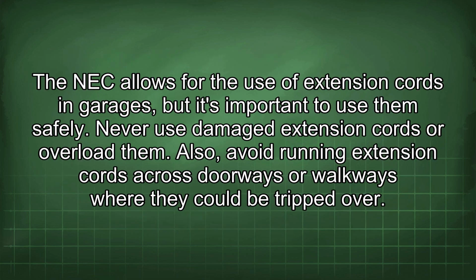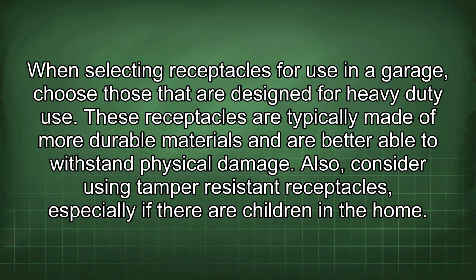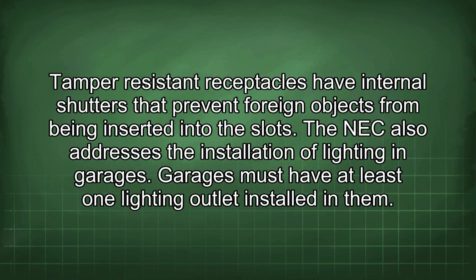The NEC allows for the use of extension cords in garages, but it's important to use them safely. Never use damaged extension cords or overload them. Also, avoid running extension cords across doorways or walkways where they could be tripped over. When selecting receptacles for use in a garage, choose those that are designed for heavy-duty use. These receptacles are typically made of more durable materials and are better able to withstand physical damage. Also, consider using tamper-resistant receptacles, especially if there are children in the home. Tamper-resistant receptacles have internal shutters that prevent foreign objects from being inserted into the slots.